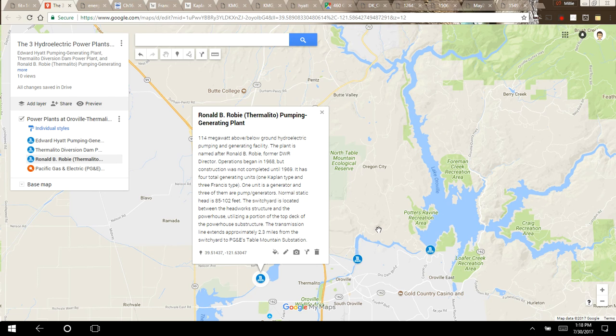It has 4 total generating units, 1 Kaplan type and 3 Francis type. 1 unit is a generator and 3 of them are pump generators. Normal static head is 85 to 102 feet. The switchyard is located between the headworks structure and the powerhouse, utilizing a portion of the top deck of the powerhouse substructure. The transmission line extends approximately 2.3 miles from the switchyard to PG&E's Table Mountain substation.